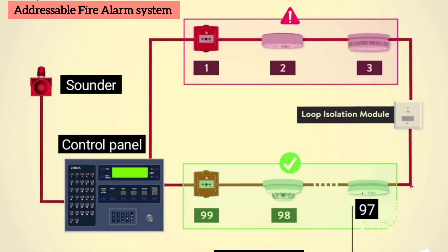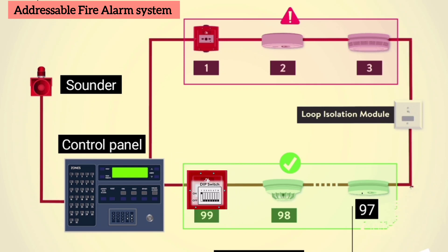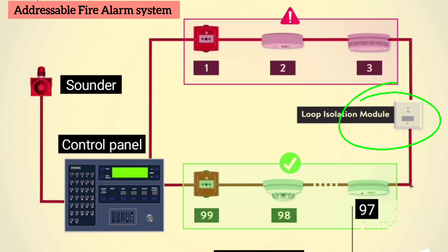Addressable fire alarm system. The detection principle of an addressable system is the same as a conventional system, except that each detector is given a set address, usually by means of a DIP switch, and the control panel can then determine exactly which detector or call point has initiated the alarm. The detection circuit is wired as a loop and up to 100 to 160 devices may be connected to each loop. It is common for the loop to be fitted with a loop isolation module so that the loop is sectioned, in order to ensure that a short circuit or single fault will only cause the loss of a small part of the system, allowing the rest of the system to function normally.